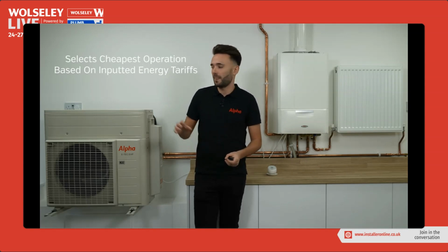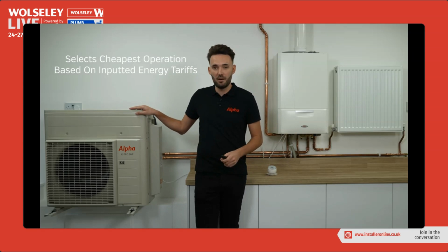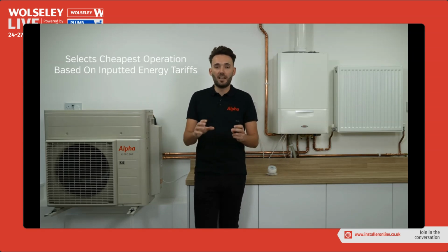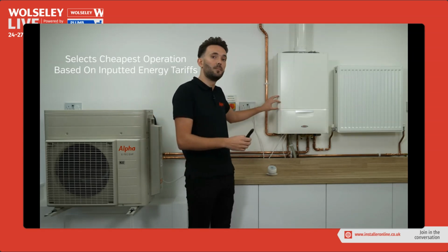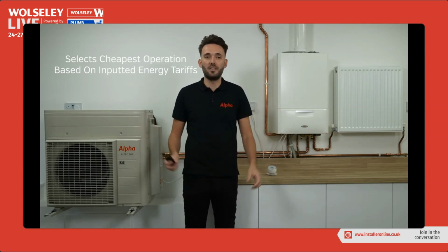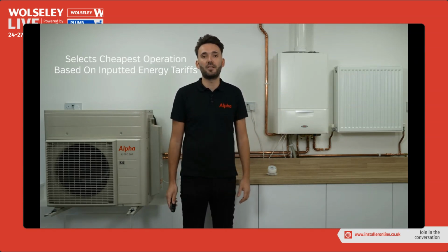It will take the COP of the heat pump, the coefficient of performance, and work out the COP of the boiler, compare them against the prices, and always use the cheapest appliance at that current time.